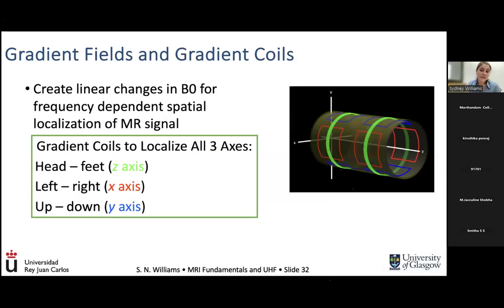So finally, the final portion of this whole system for the MRI hardware is the gradient coils, which will generate the gradient fields. The gradient coils are also inside the bore of the magnet, and there's a nice pictogram on the right here that shows you their orientation. They are designed to cause a linear shift in the magnetic field along the three spatial dimensions. So you have X, Y, and Z. You'll create these linear shifts, and we do this deliberately while imaging because then we'll be able to tag essentially different parts of the body so we can localize where the MRI signal is coming from.